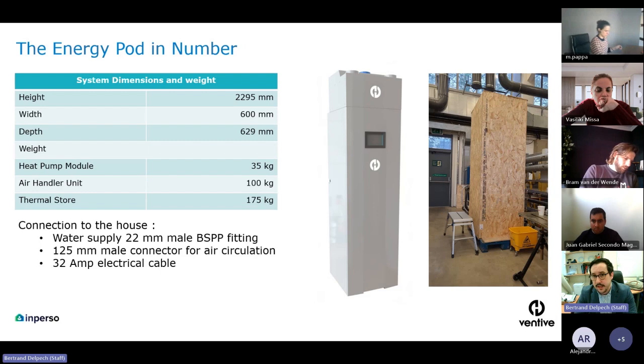The connection to the air circulation in the flat and on the outdoor air draw is a 125 mm connector, so you can just put a spigot on top of it and then connect it to the air system. The supply is a 32 amp electrical cable. We have a fuse inside, which is 32 amp. So we need to have the appropriate sizing in terms of power supply to the system.